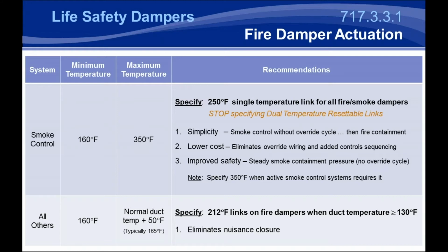Now, of course, it makes sense that you don't want a fire damper closing as you're exhausting that hot smoke. So you're allowed to set the fire dampers to either 250 or 350, depending on the application of the smoke control system and the rating that it's set to.